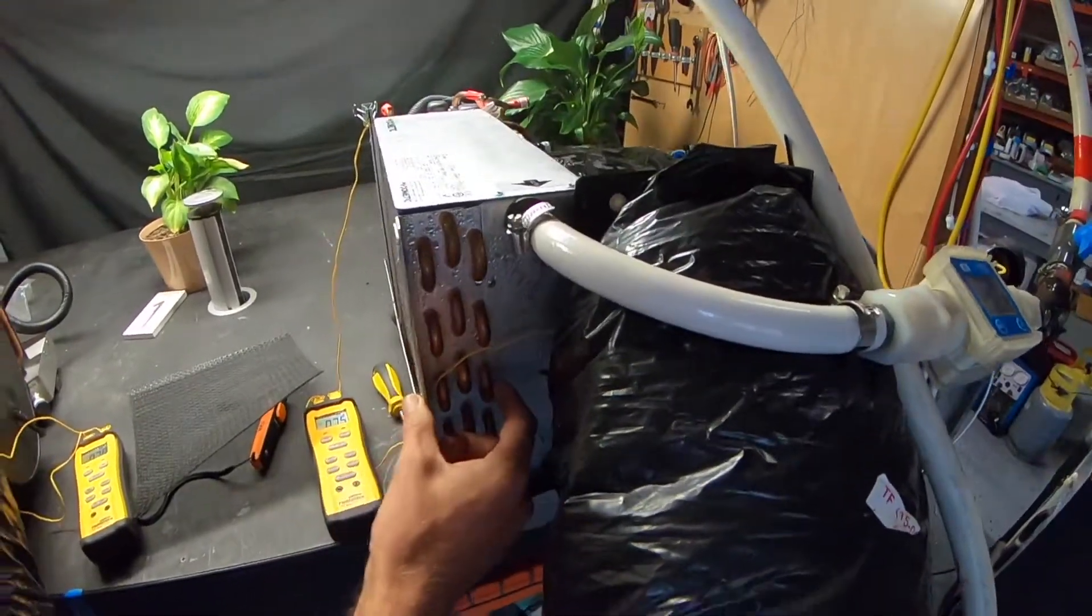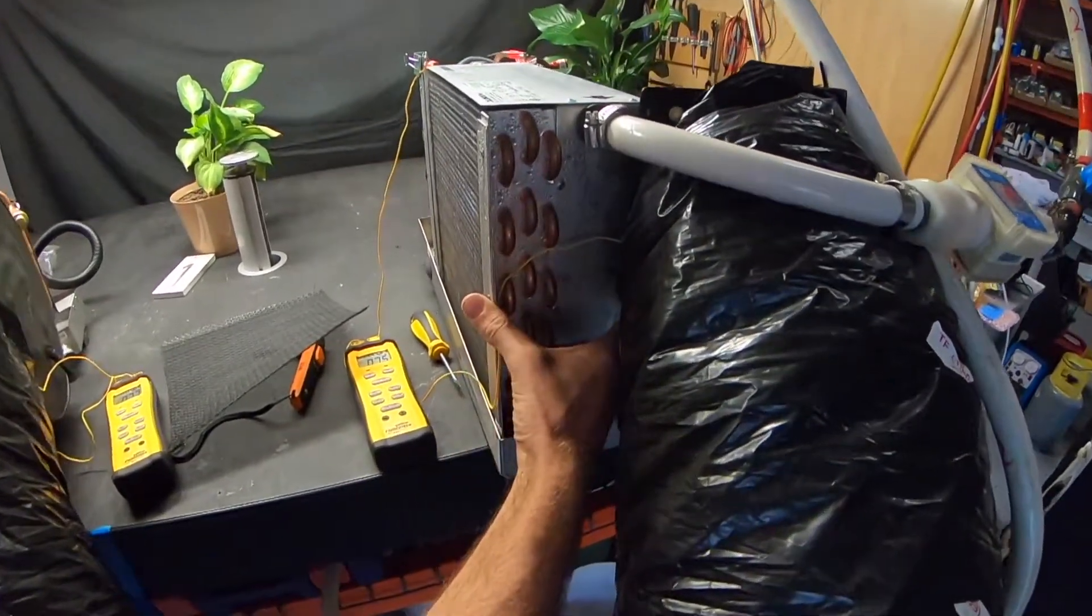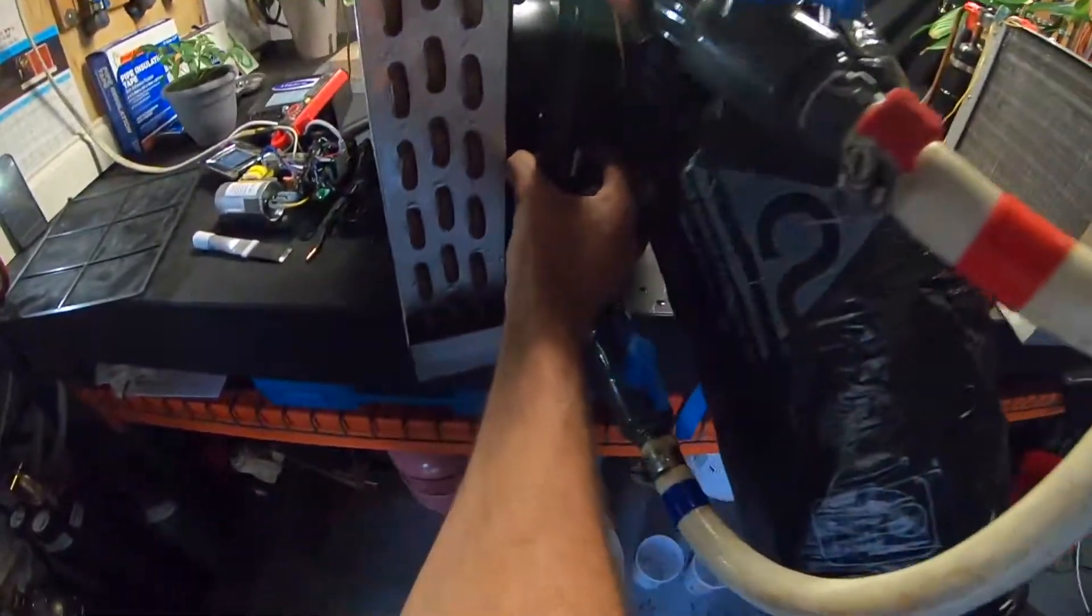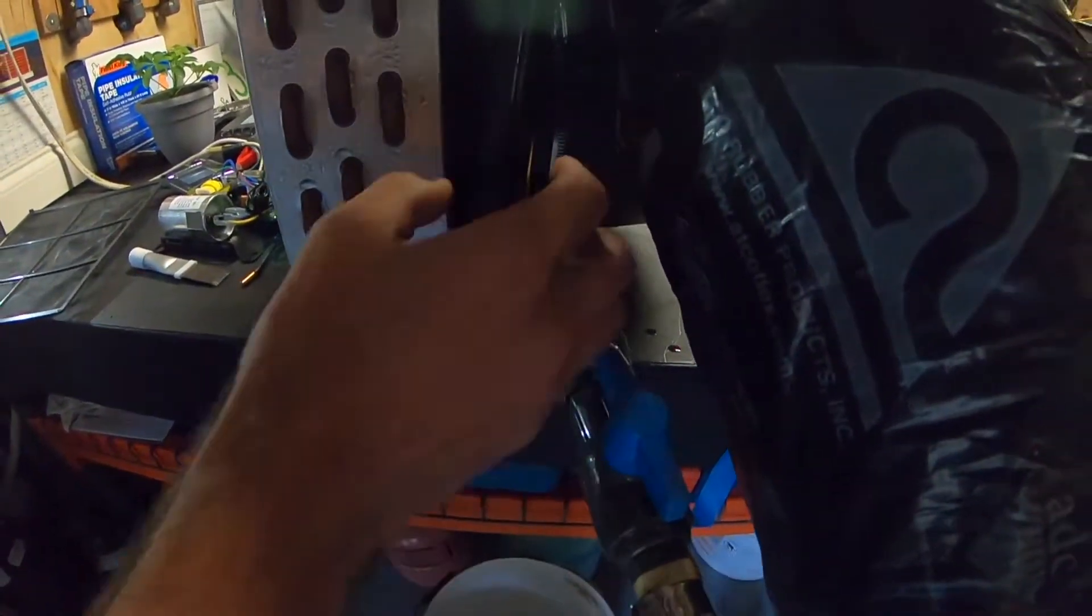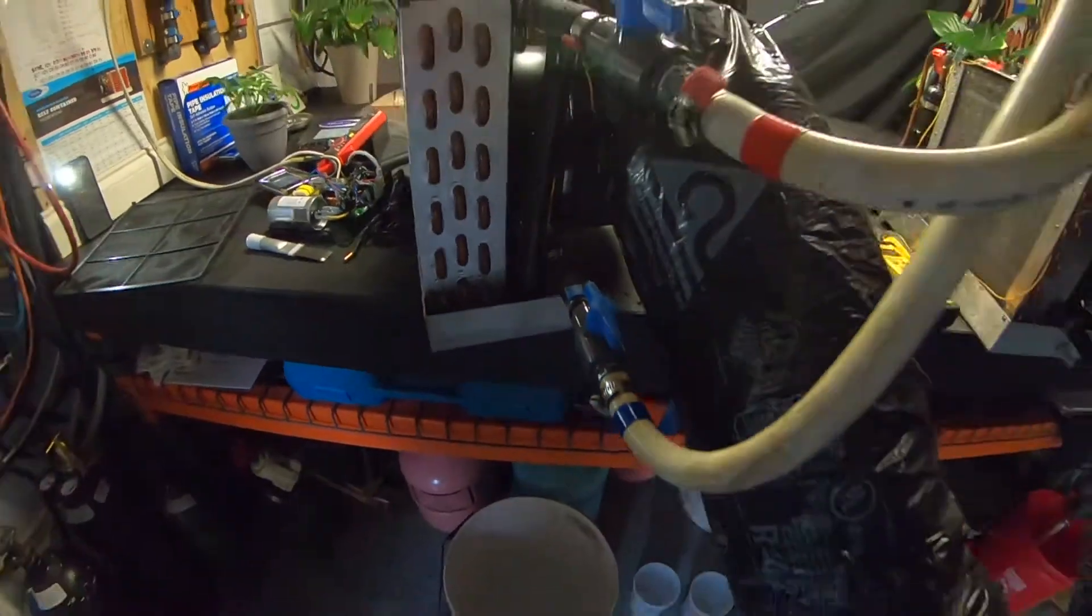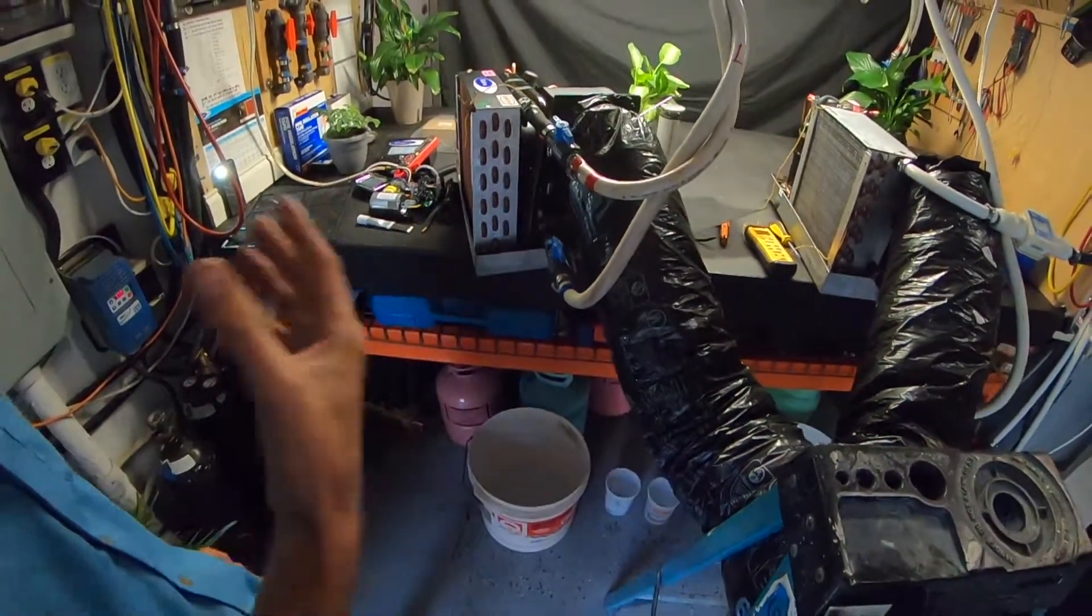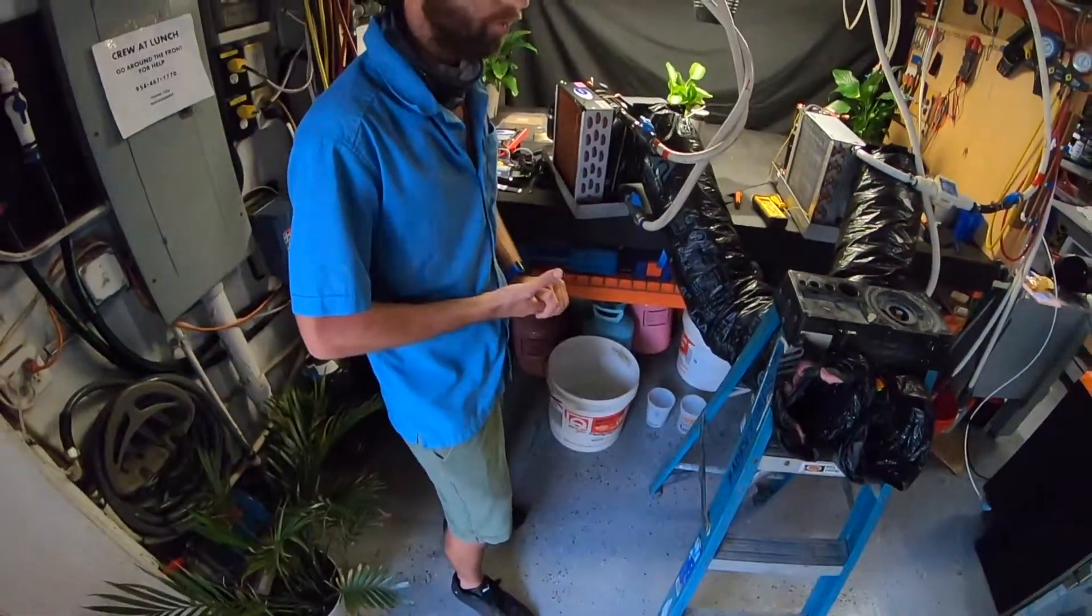The other thing is the spacing between the evaporator here and our blower. You can see how much space we have over here, so we don't have liquid that comes out of the blower. We maintain very dry air coming out of the unit.